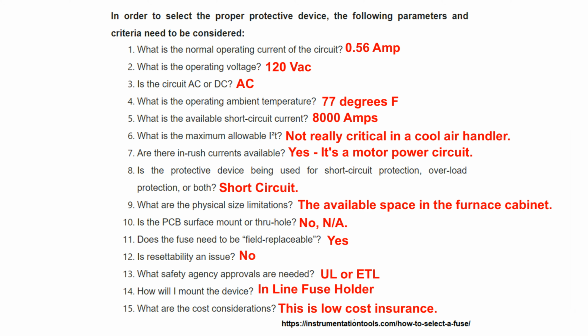What is the available short circuit current? It's 8,000 amps. 8,000 amps, what? I'll explain that momentarily. The maximum allowable I squared T is not really critical in a cool air handler. Are there inrush currents available? Yes, it's a motor power circuit. Motors have inrush. Is the protective device being used for short circuit protection, overload protection, or both? I'm using it primarily for short circuit protection.